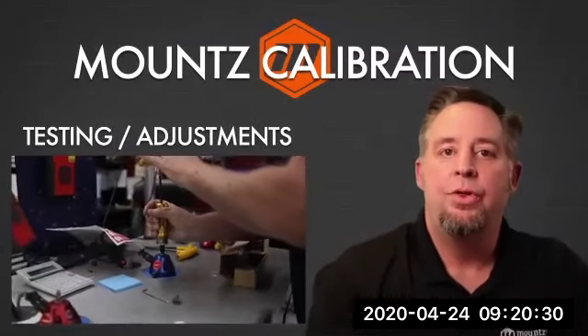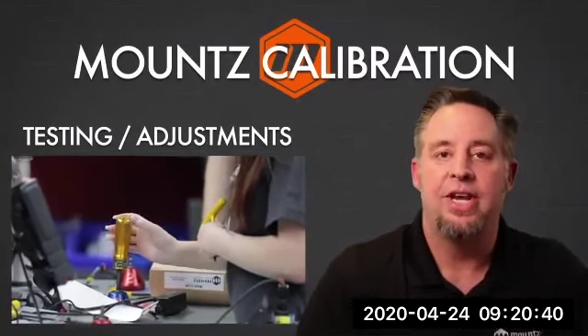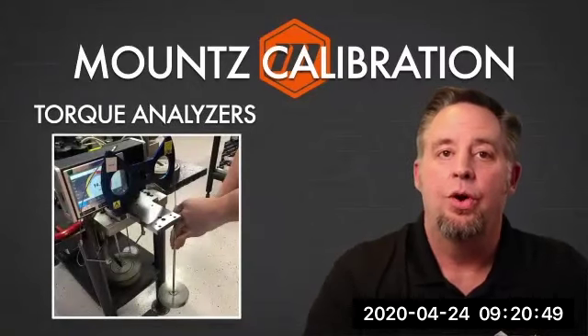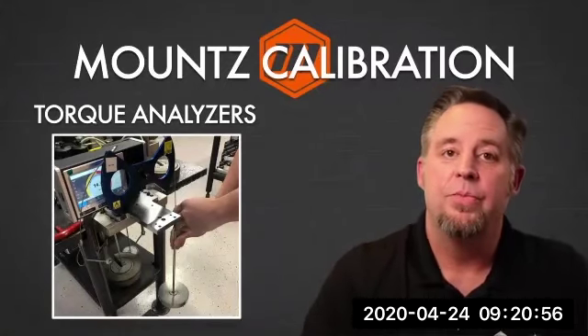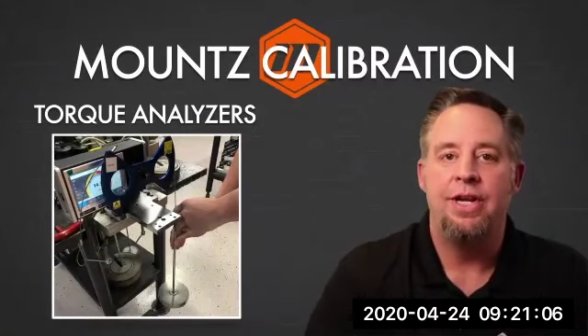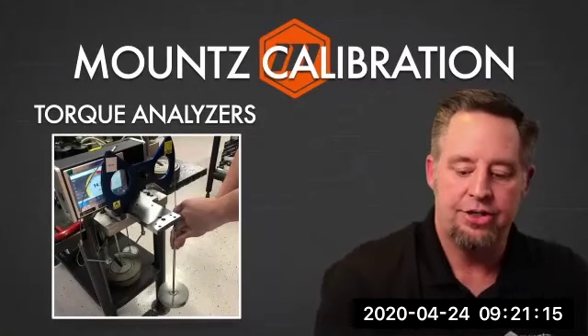So at that point, there's going to be some testing and adjustments that are done, depending on what type of tool it is, whether it's a hand tool or a torque analyzer. So for example, if we're going to be doing an analyzer, this gives you a little bit of the process here. Typically, you would have the analyzer with a wheel at a determined length, and then you're going to be adding weights to it to calibrate it at certain set points for the analyzer. So that's how typically analyzers are calibrated as compared to the hand tools.